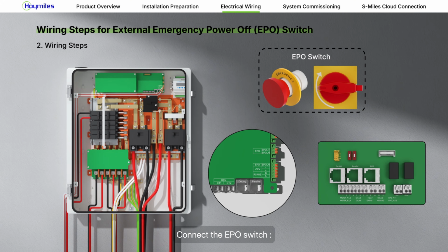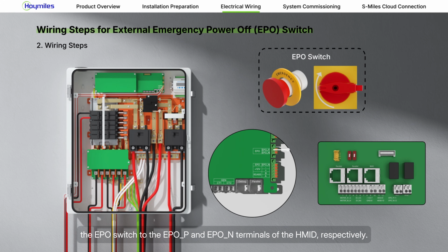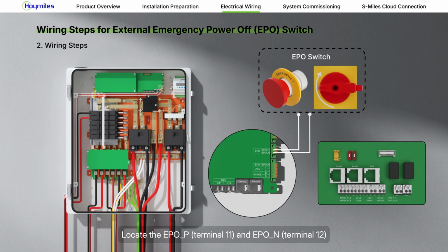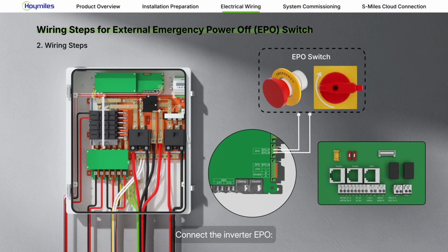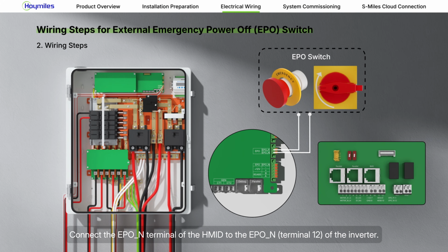Connect the EPO switch. Connect one pair of wires from the EPO switch to the EPO-P and EPO-N terminals of the HMID, respectively. Remove the inverter jumper. Locate the EPO-P and EPO-N on the Hoymiles energy storage inverter and remove the jumper. Connect the inverter EPO. Connect the EPO-N terminal of the HMID to the EPO-N of the inverter.